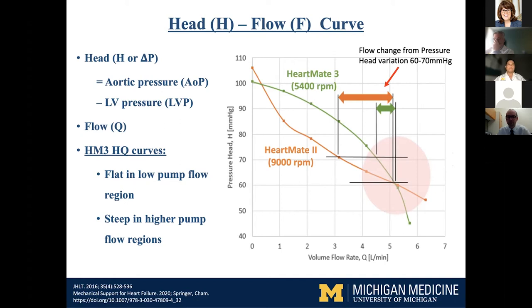At the operating ranges, the HeartMate 3 is more resilient to changes in head pressure, which is what you want in a pump. It's different depending on your pump speed and the kind of pump, and it's basically ingrained in the pump design itself — something that engineers really try to optimize.